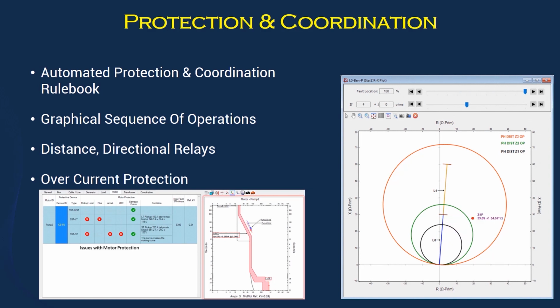let's take a look at protection and coordination analysis, which provides the protection engineer with the ability to automatically check existing protective device settings based on industry guidelines and standards. These guidelines are automatically included in the rulebook and are taken from standards such as IEEE, IEC, NEC, and other local standards.